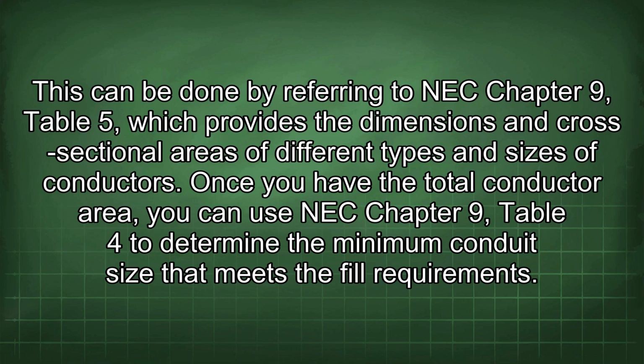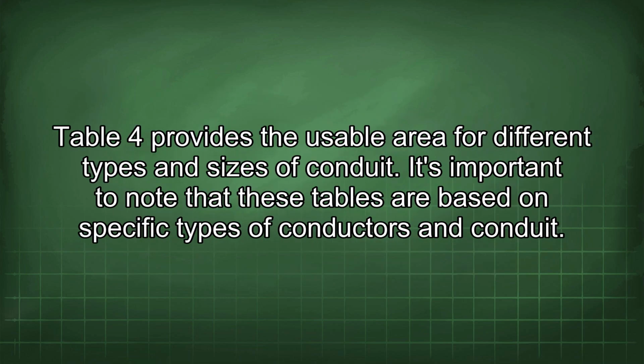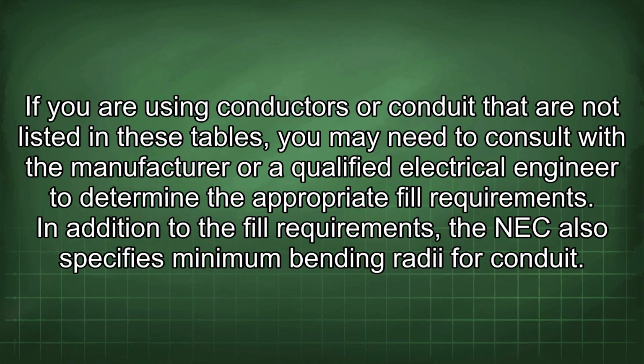Once you have the total conductor area, you can use NEC Chapter 9, Table 4 to determine the minimum conduit size that meets the fill requirements. Table 4 provides the usable area for different types and sizes of conduit. It's important to note that these tables are based on specific types of conductors and conduit. If you are using conductors or conduit that are not listed in these tables, you may need to consult with the manufacturer or a qualified electrical engineer to determine the appropriate fill requirements.